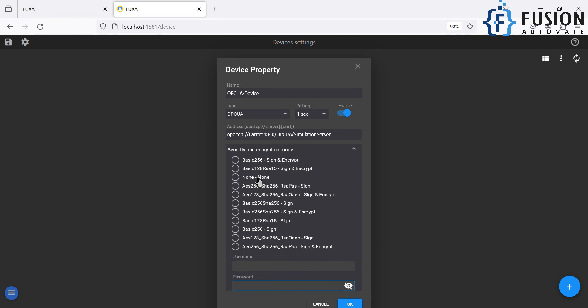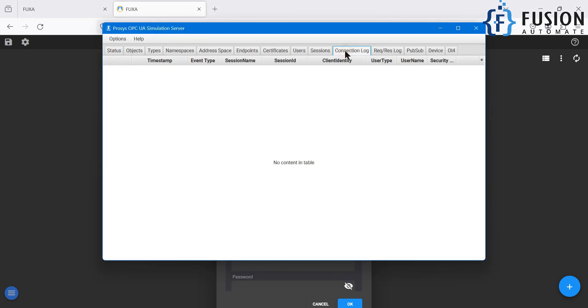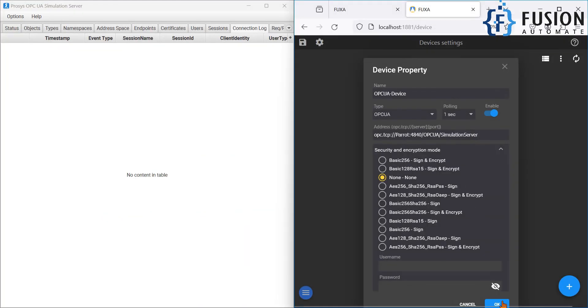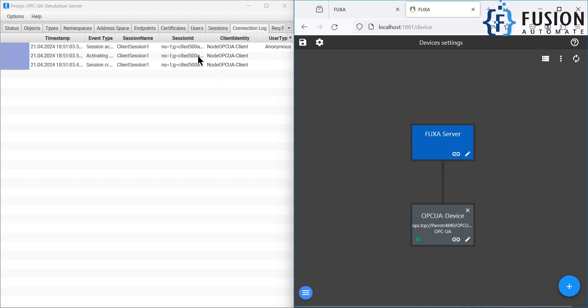I'm going to select security policy and message mode as None. If I go to the Prosys OPC-UA Simulation Server connection log, you can see there are no connection logs because no one has connected yet. I'm going to open both windows in parallel and click OK. You can see we instantly have three connection log entries, and the green LED is on — this means we have successfully set up the connectivity between the Prosys OPC-UA Simulation Server and FUXA SCADA.